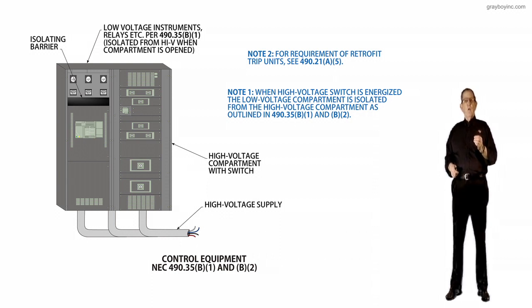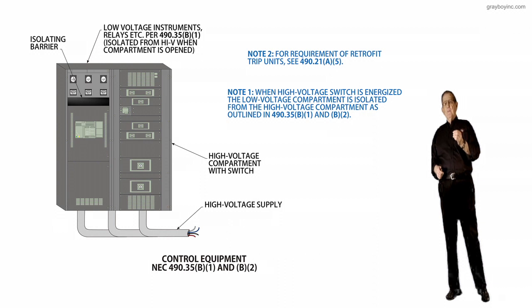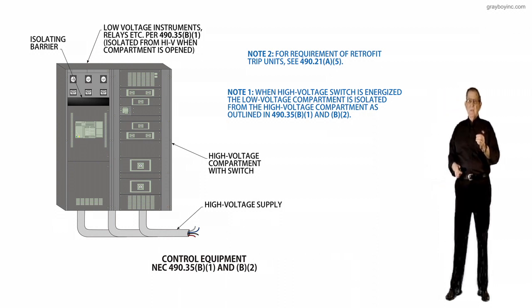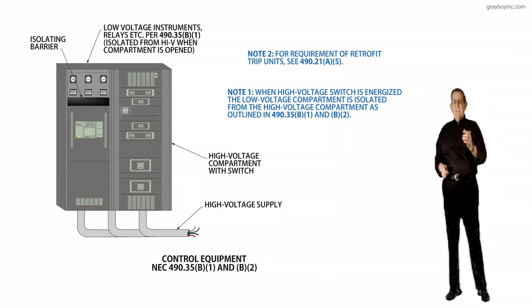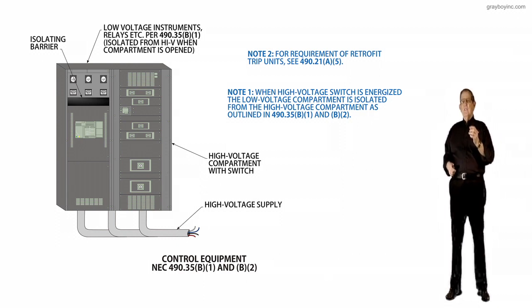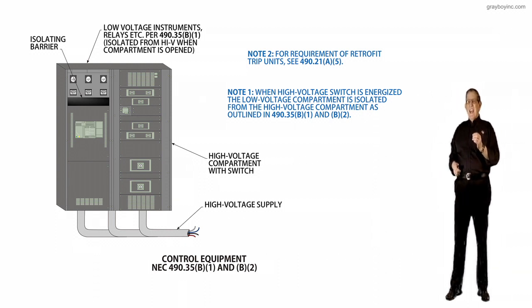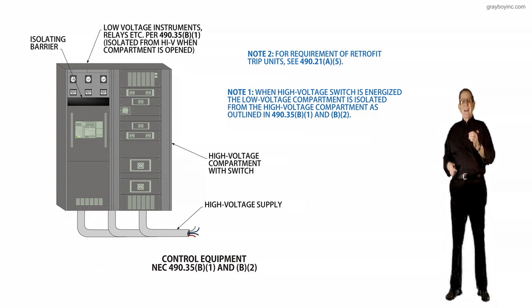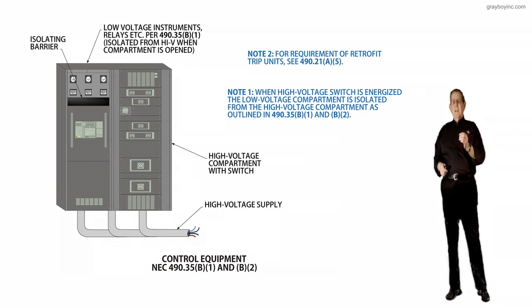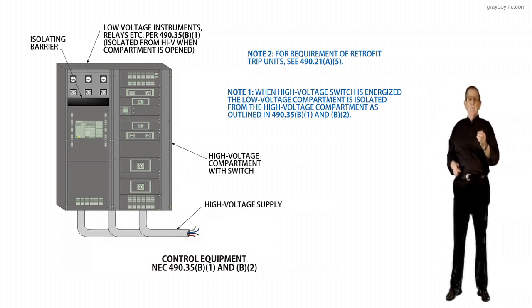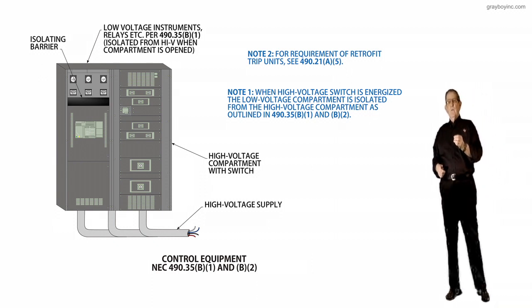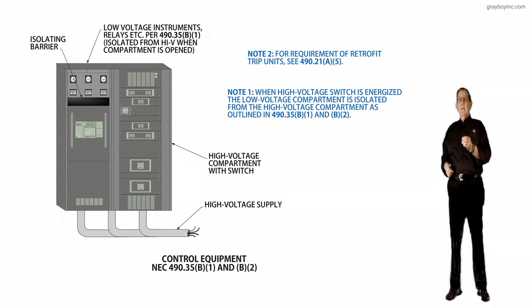Condition 1 requires interlocking to prevent an access means from being opened or removed at any time. There is no allowance to open the access means even if the high voltage switch or disconnect is in the isolating position. Condition 2 requires that when the switch and disconnecting means is in the non-isolated position, there can be no low voltage parts in the compartment, which would require the parts to be moved from the compartment when the switch is moved to the isolated position.